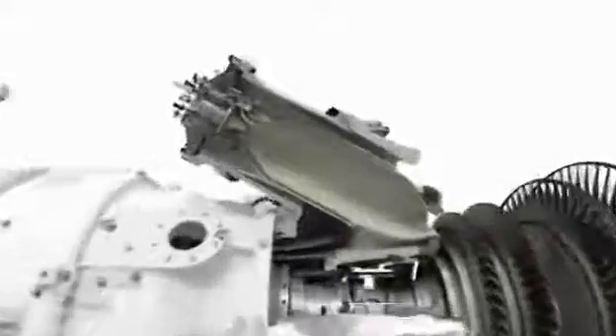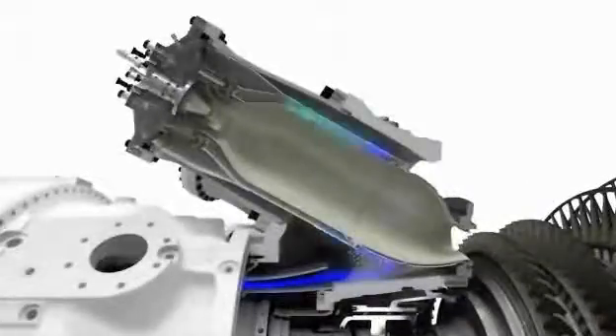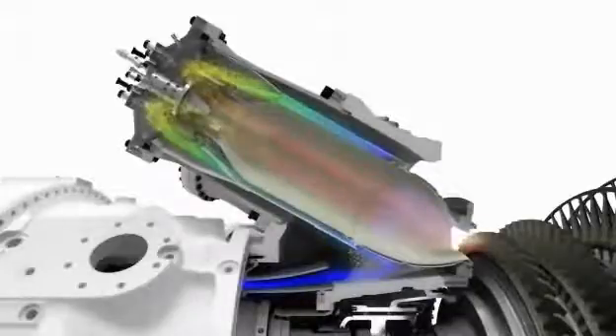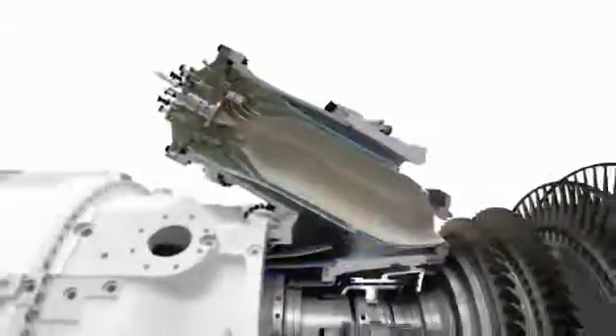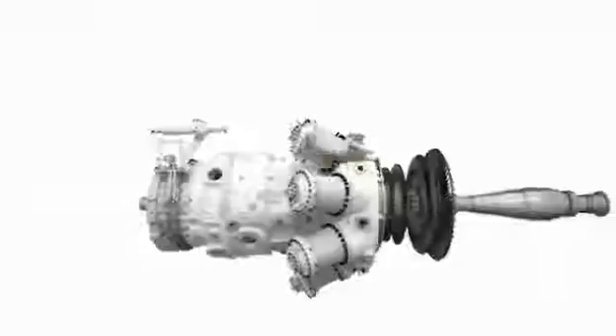Here we make maximum use of the fuel input while ensuring that both NOx and CO2 levels are kept under control. DLE, dry low emissions combustion, is used in 100% of all SGT 700 and SGT 800 installations, and since 1990, it's also the standard combustion method used in the SGT 600. The DLE turn-down capability enables the use of large single turbines replacing multiple small units, allowing the same operating envelope. It offers robust and stable operation with dual fuel online switchover capabilities.